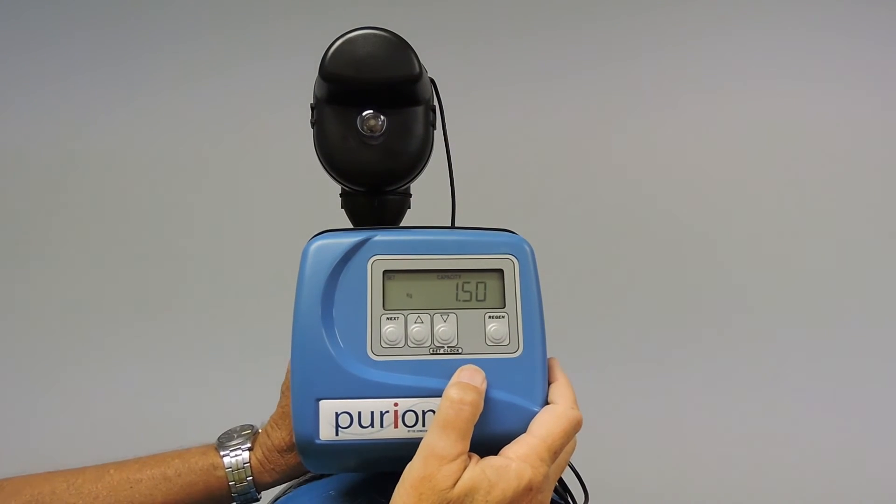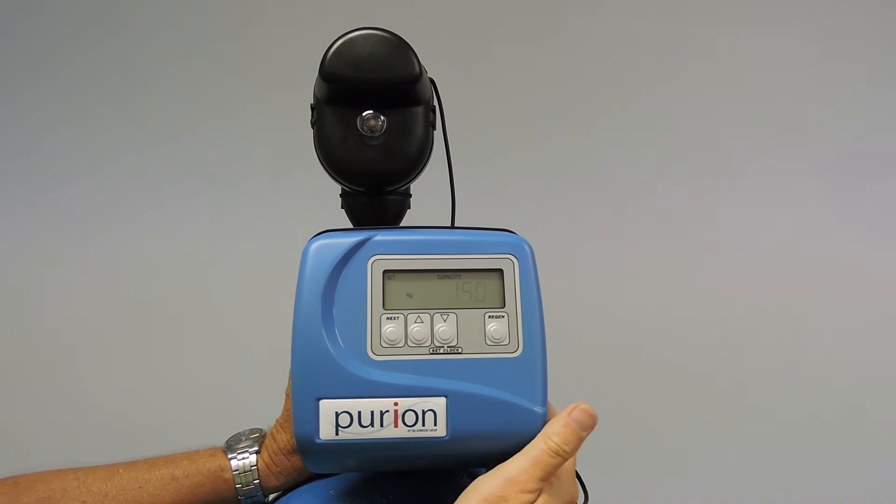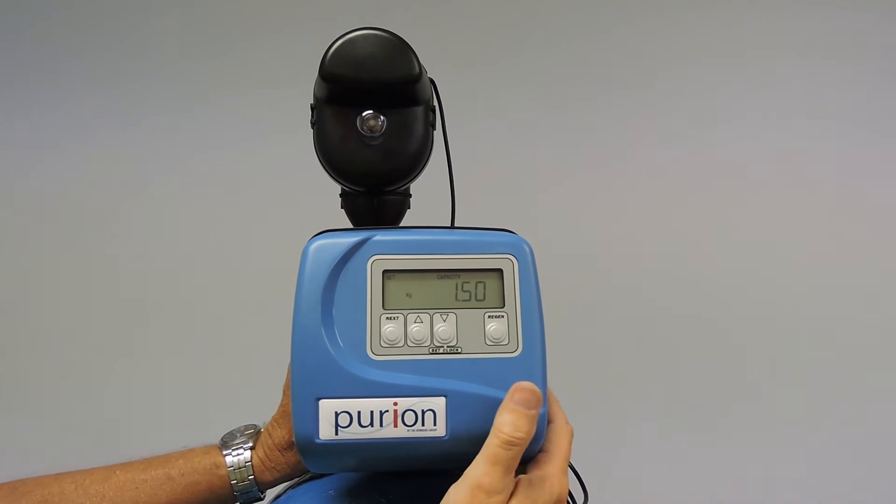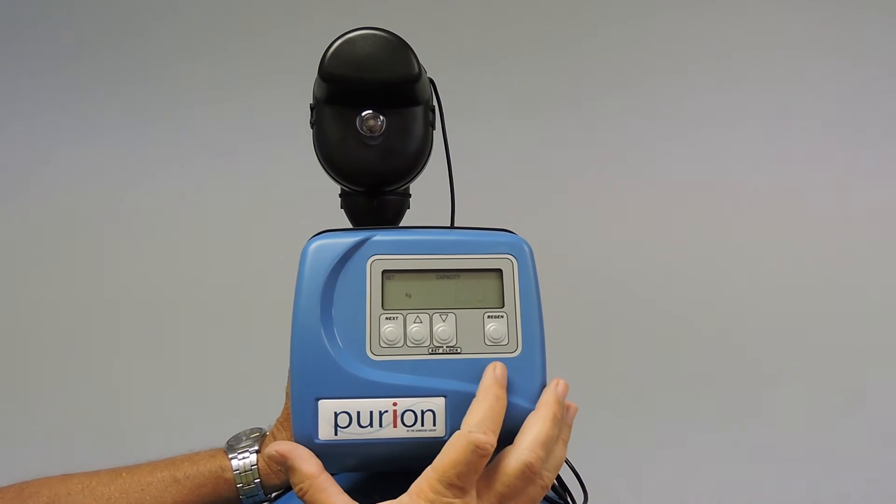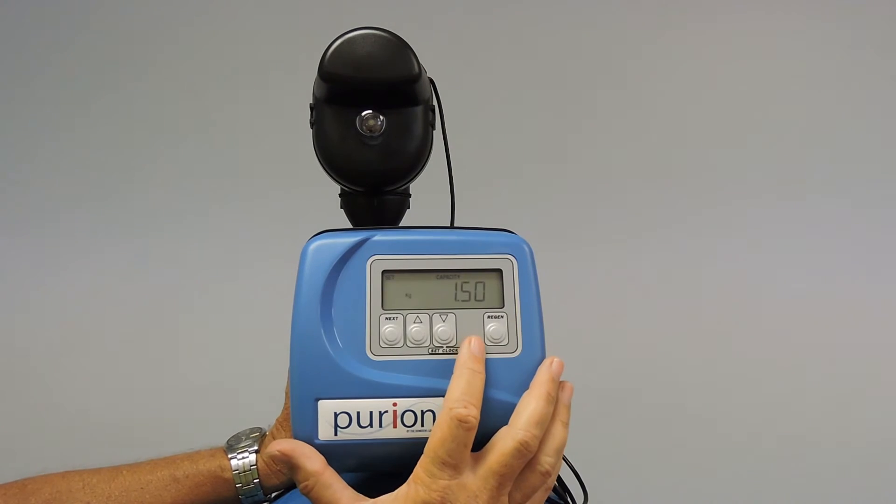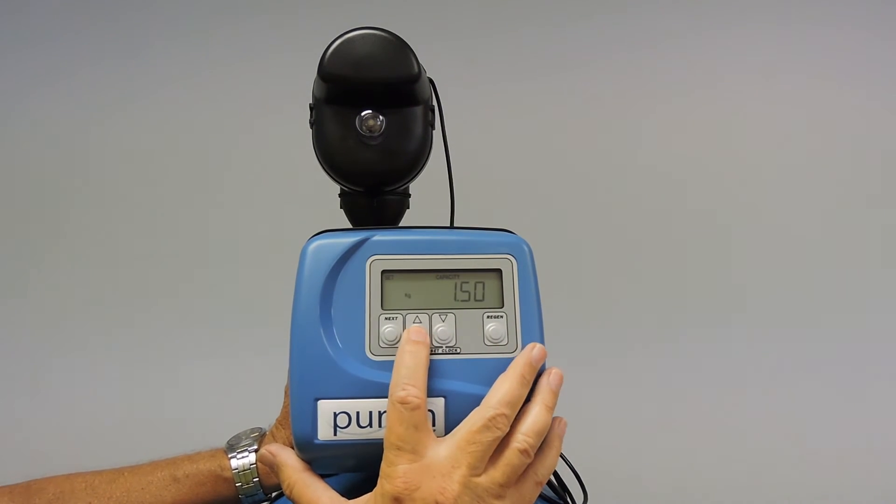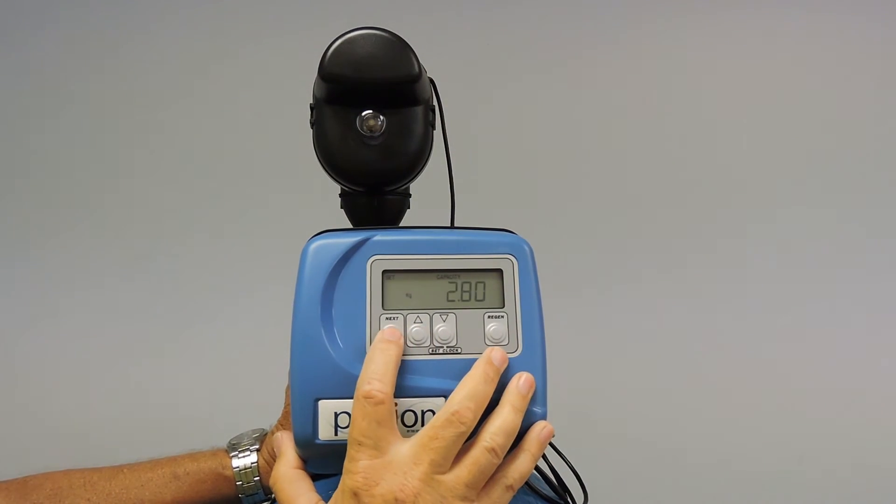And now we're into capacity. This is capacity of exchange hardness. We've calculated 12 inch softener to be able to remove 2.8 kilograms of calcium magnesium hardness. So we will arrow up. And accept.